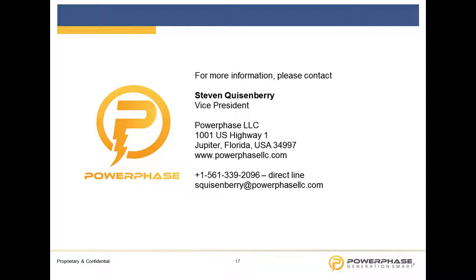Okay, cool. And one here on environmental emissions. How does Turbophase impact environmental emissions? Does NOx increase with Turbophase? So with that, it's a good question, and especially for folks where permitting is a concern. So the ppm value of NOx, CO, SO2, and particulate matter does not change in your gas turbine. The combustor, as Gregor's mentioned, is designed for a larger mass flow. We're just adding mass, keeping firing temperatures the same.